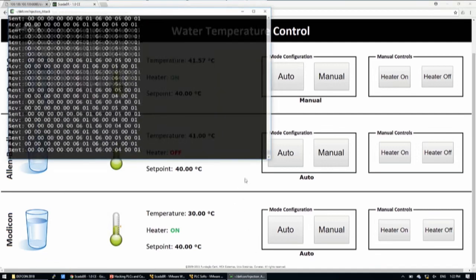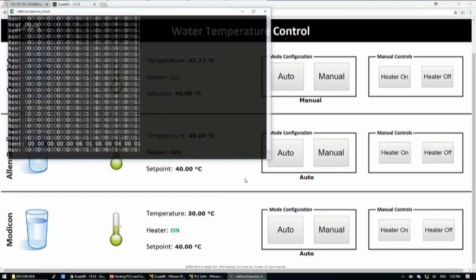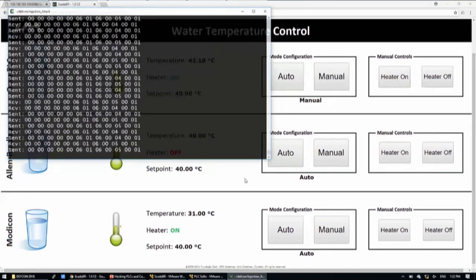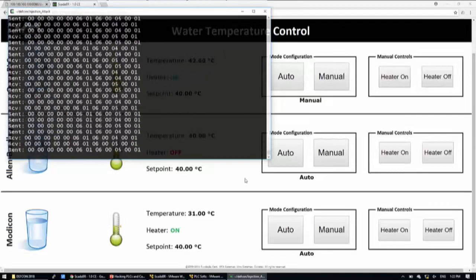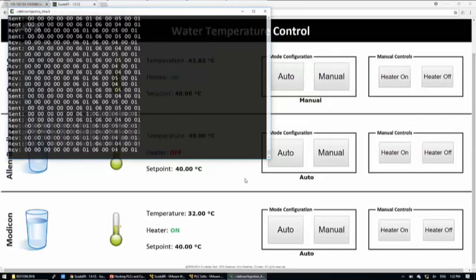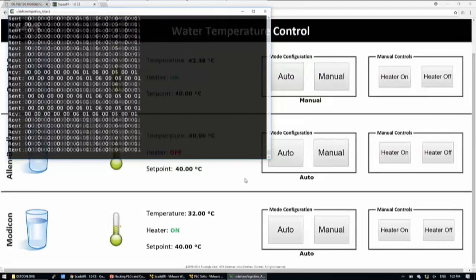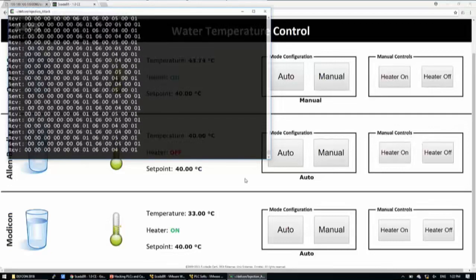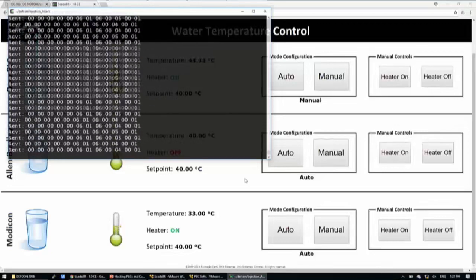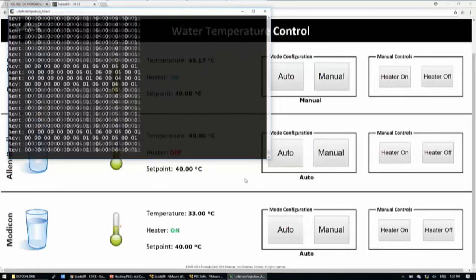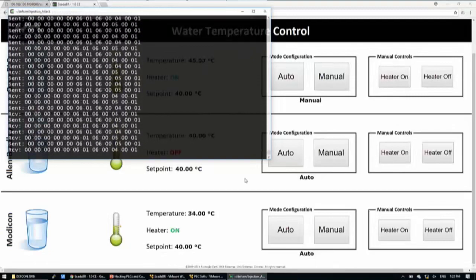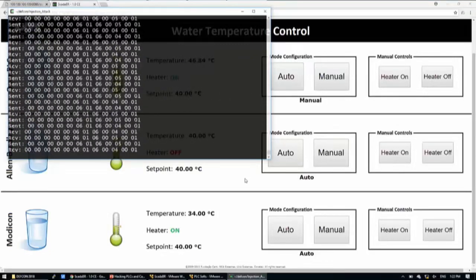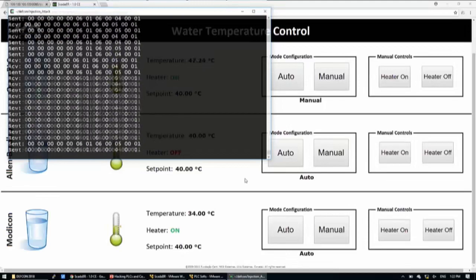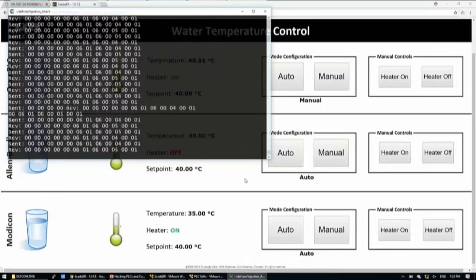And all it takes is sending Modbus frames. That's all it takes. What I'm doing here is writing to a portion of the PLC's memory that I know stores the setting for manual or auto mode, and another area that stores the setting for whether the heater is on or off. That's all it takes. And I can guarantee you this kind of attack works with 100% of the PLCs that I know of.